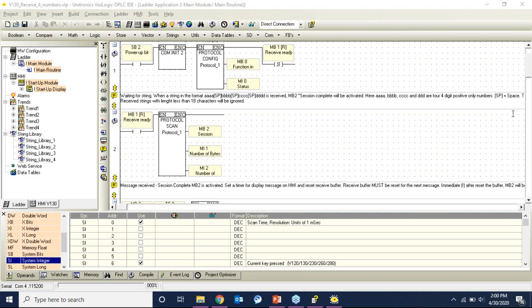One thing I failed to mention: serial communication is half-duplex — one master, one slave. In an Ethernet-based application, you can actually have a multi-master setup. You can set up two different sockets to be a master and a slave, and vice versa on the other device, so both devices can act as a quasi-master, which might be helpful in some cases.